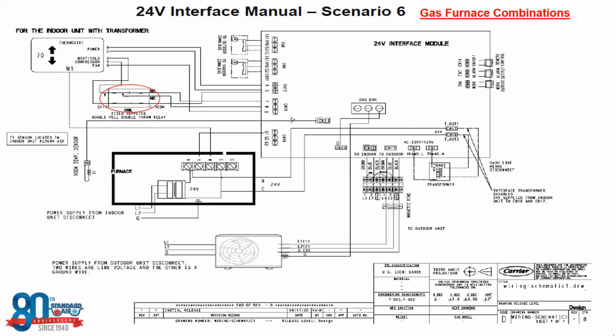This is something that you can set up through your third-party thermostat, of course, depending on the thermostat that you're using. The factory does recommend, just because of how heat pumps deal with defrosting and downtimes with defrosting, that when the outdoor temperature is below 32 degrees, that you switch over and allow the thermostat to kick on the gas furnace while shutting the heat pump off, so we don't have to worry about any defrosting times. Okay, but again, that depends on how you guys want to run that system.